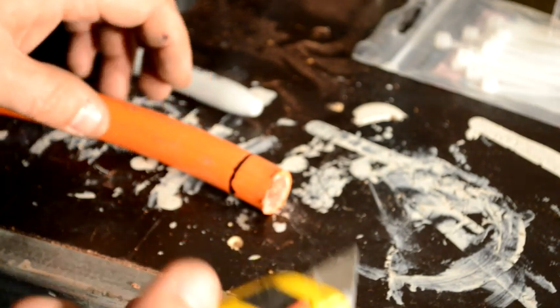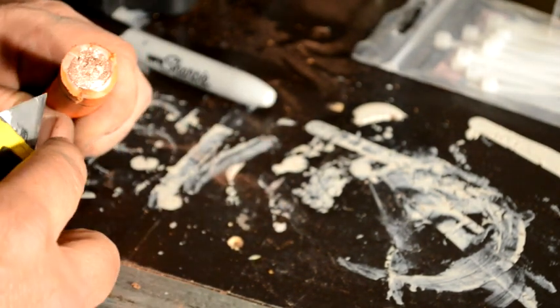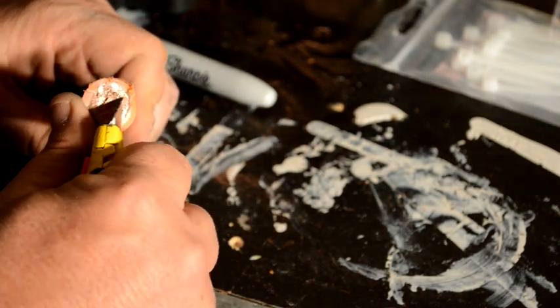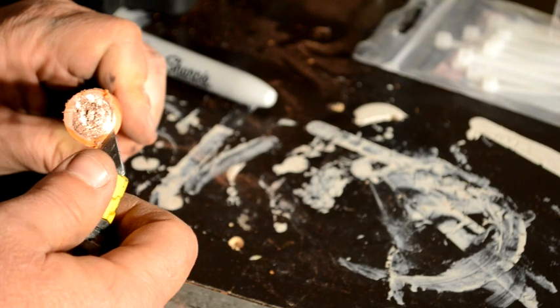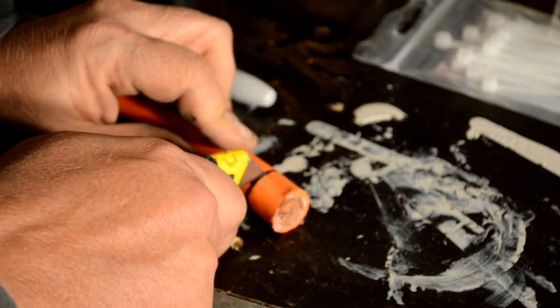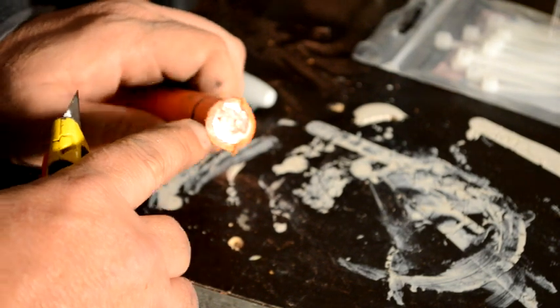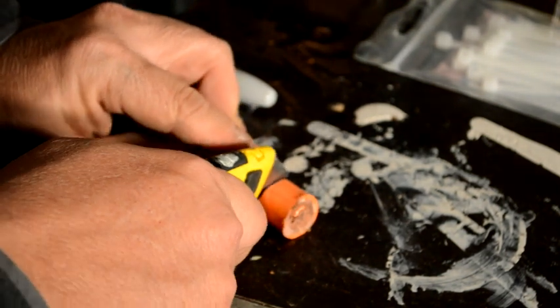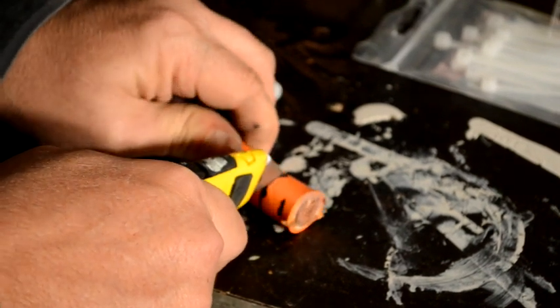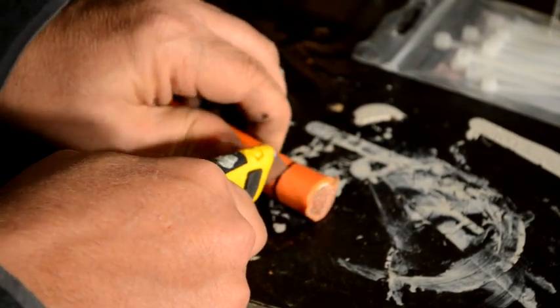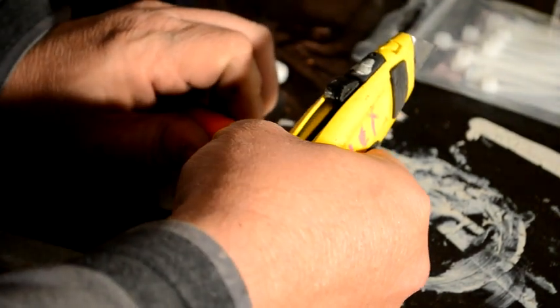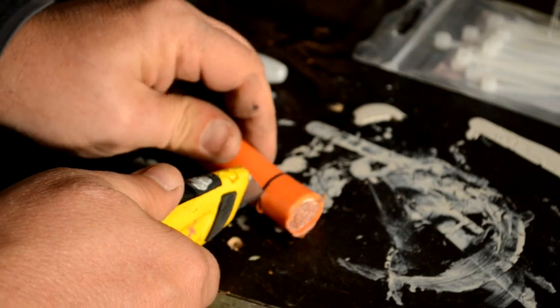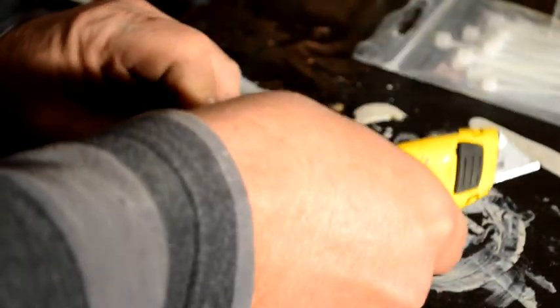So the next thing you want to do is grab yourself a blade and we're going to take off this outer insulation up to that line. And you'll see with this particular cable, which is important for using this particular technique, is that it has an outer orange insulation and an inner white insulation, so it's a double insulated single core cable. And what we want to do, if your cable is just single insulation, you might skip this step and move on to the next step. What we want to do is cut through just the orange outer insulation with our knife, being careful not to cut through the second layer, and obviously being careful not to cut through to the copper.